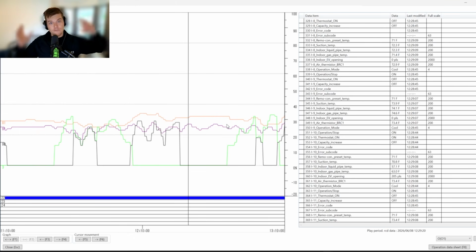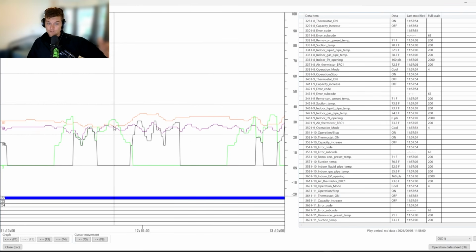So there you go. Rock skip method, call it whatever you want to. Bounce method, squiggly wiggly method. It's whatever you want to say. It's just to tell you that there are too many variables moving within a natural system to then just look in and hone in on low suction superheat. Because when the suction superheat was low, guess what? The discharge superheat was also low here. If I go and look at that, you'll see the discharge superheat go like this. So we know there's liquid there.